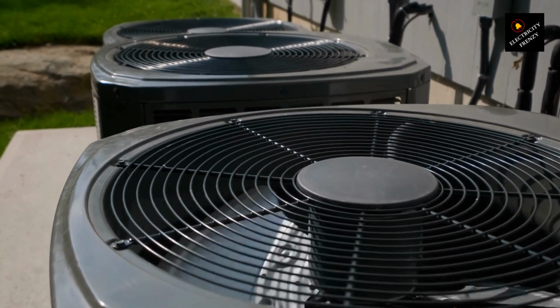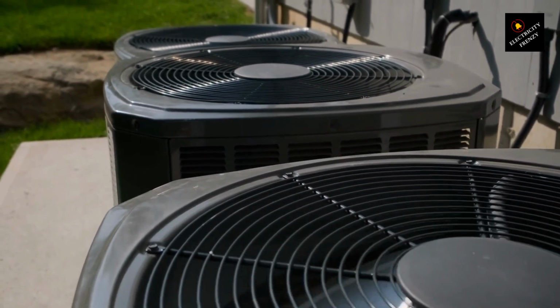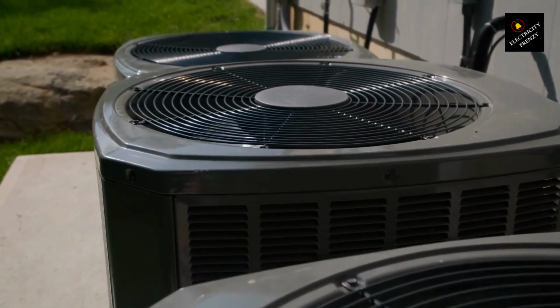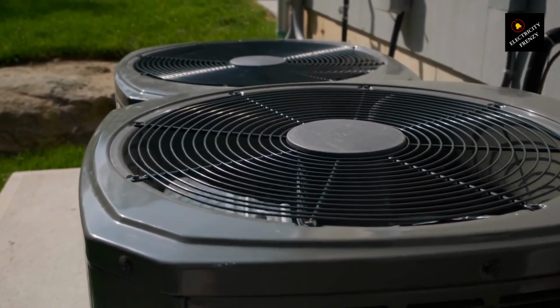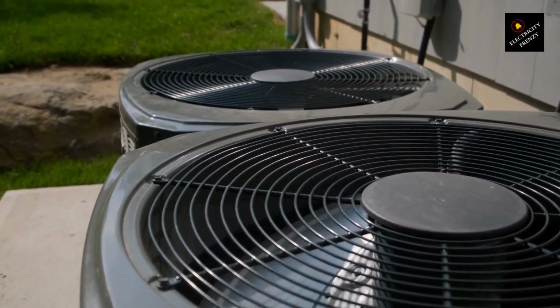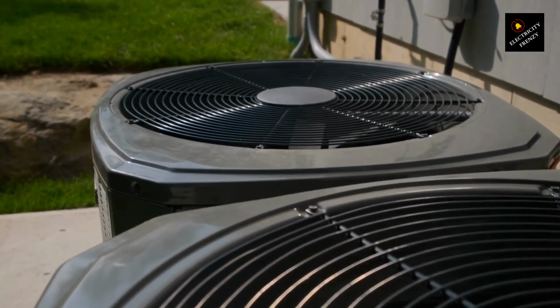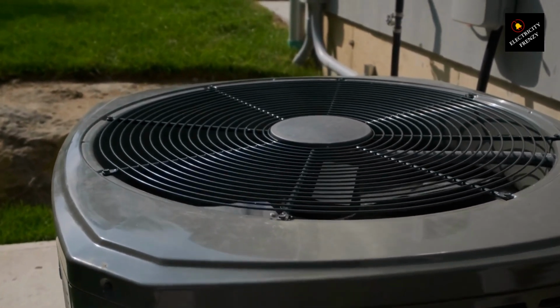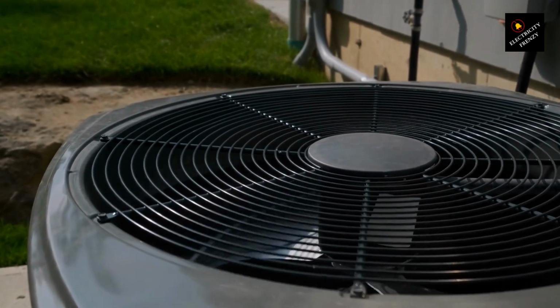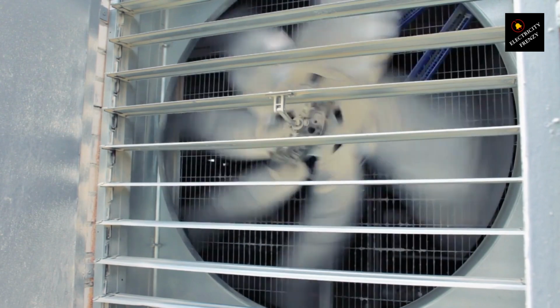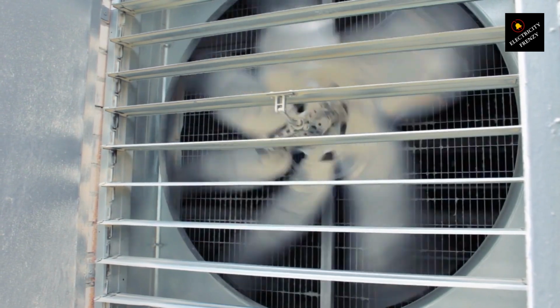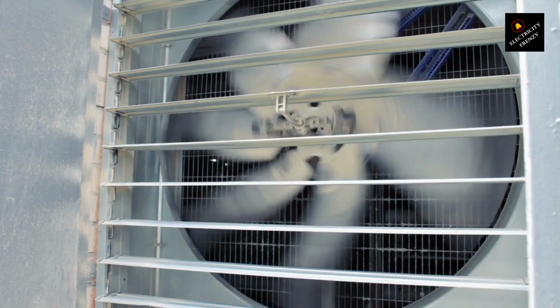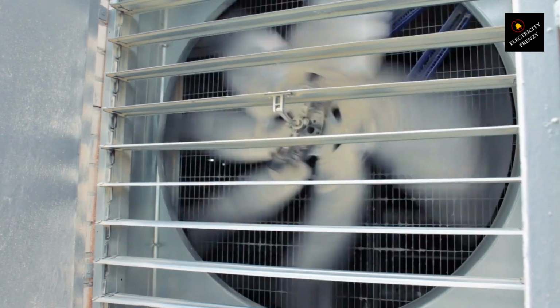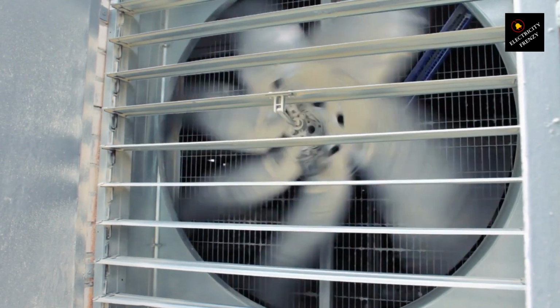If the breaker is worn out or has a weak tripping mechanism, it may trip unnecessarily, even with a normal electrical load. To diagnose a faulty circuit breaker, you can visually inspect it for any signs of damage, such as burnt marks or a loose connection. Use a multimeter to test the voltage and continuity of the circuit breaker. If it consistently trips at a lower current than its rated capacity or shows abnormal readings, it indicates a faulty breaker. Solution: if you suspect a faulty circuit breaker, it's advisable to consult a professional electrician to replace it. The electrician will ensure that the new breaker is properly installed and meets the electrical requirements of your air conditioner unit.